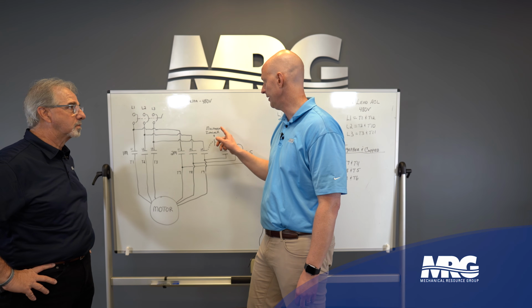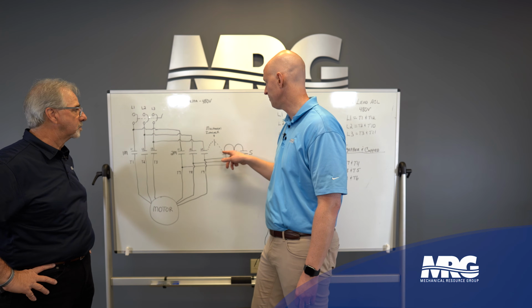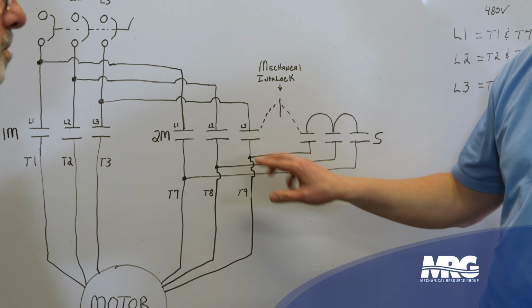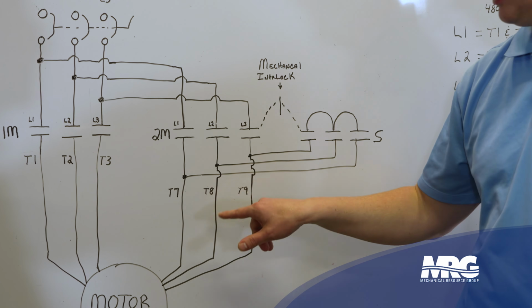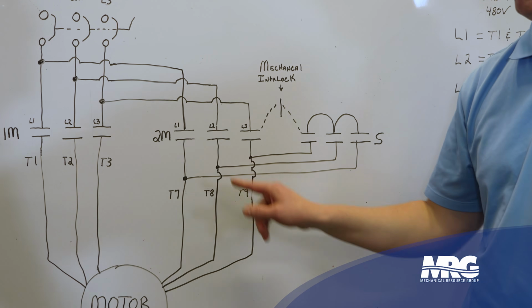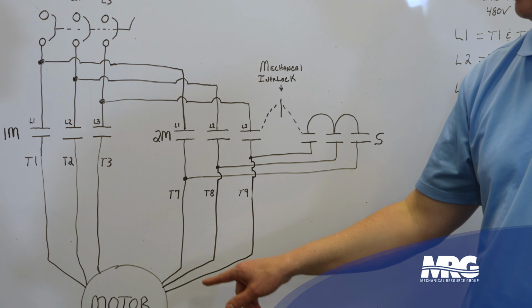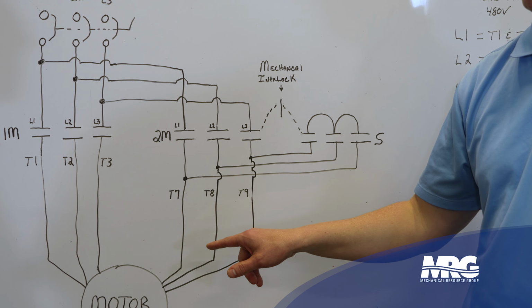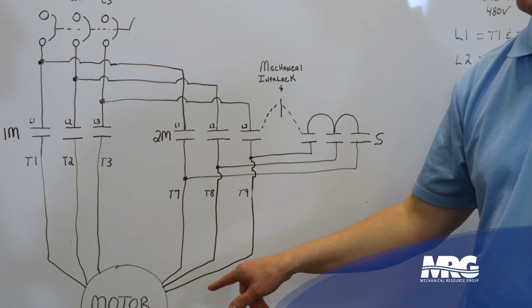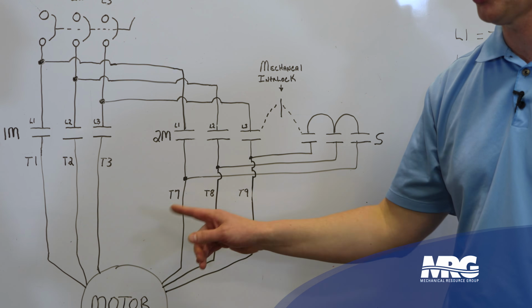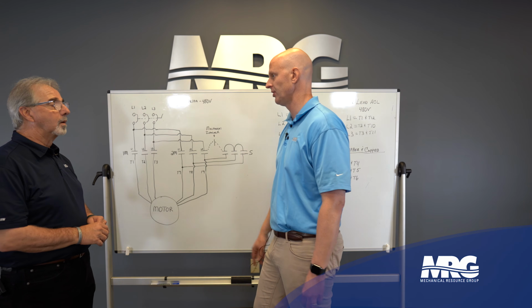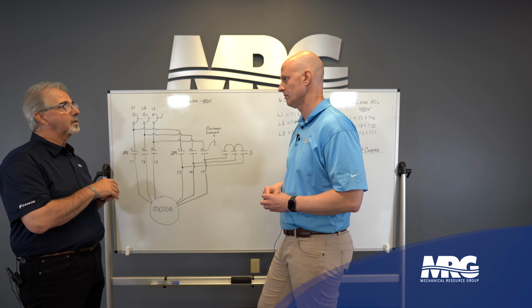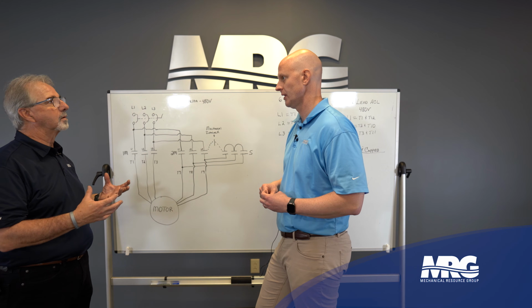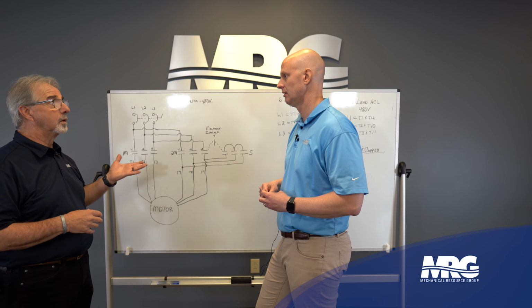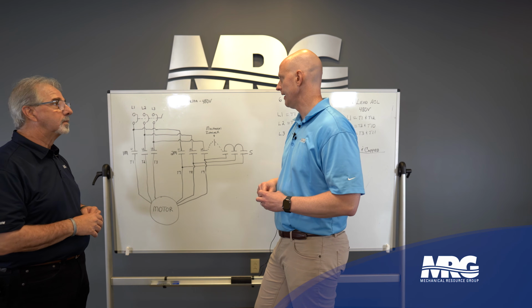And then once we get inertia and the interlock times out, then we open that short, and then we're closing the M2. Correct. And we're able to get full current and capacity out of the motor, but it's a much reduced inrush current because we got that motor started and then the momentum's already going. Right. What we're doing is we're calculating when we want to apply torque. Yeah. Is what we're basically doing, and we're doing it through timing. Okay. Okay. And I hear what you're saying.